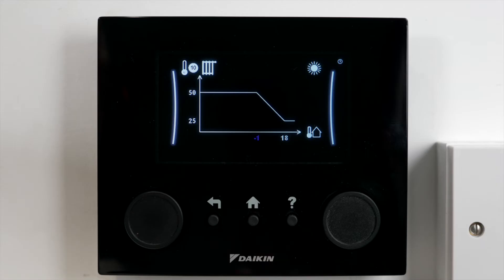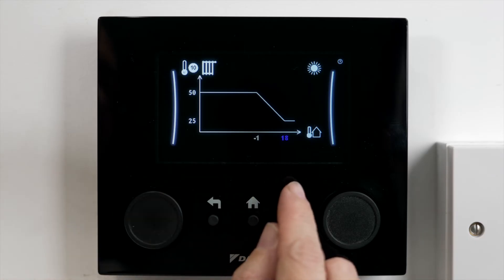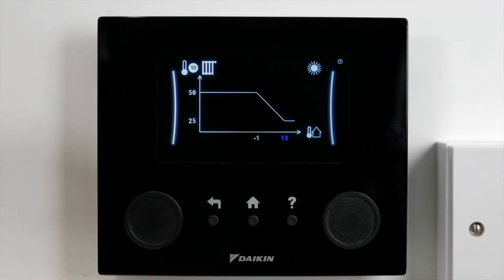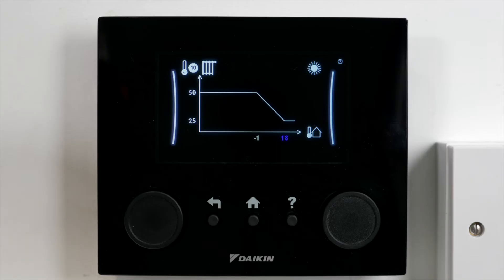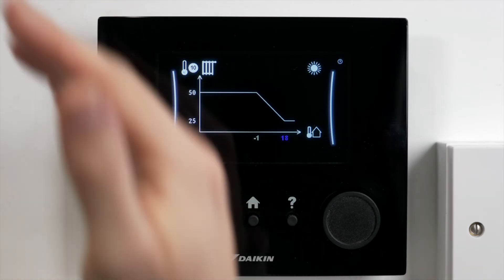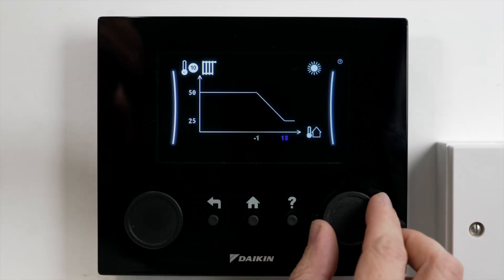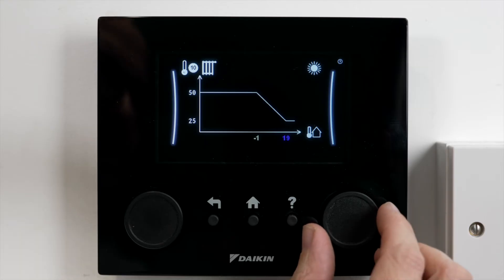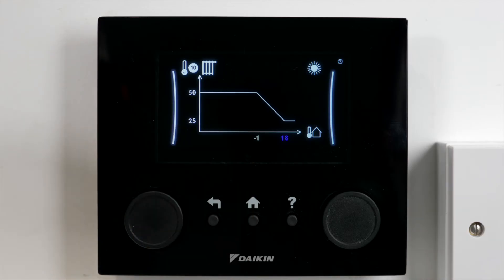I'm going to start with minus one, then go across to the next one — this is the temperature at which I want the curve to start ramping up. So when it starts to get a little bit colder outside and I want to be warmer inside, when do I want this heat to start ramping up to heat my house? I'm going to start this one around about 18 degrees, so when it's 18 degrees outside it will start to ramp up the leaving water temperature and heat my house, giving me thermal comfort.